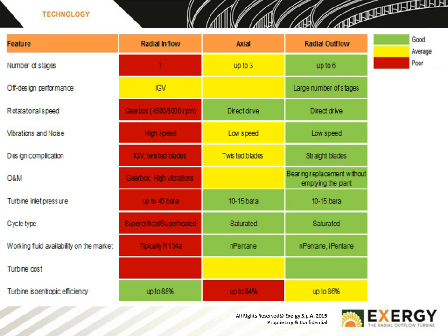We've managed to provide a very simple O&M strategy where the only parts of the turbine which need maintenance can be removed in a single unit. We call that the mechanical group. It contains the bearings, the oil lubrication system, and the seals. And those can be removed and replaced in a single block in approximately 6 hours, without losing any organic fluid. So the only maintenance on the turbine is a very, very simple procedure.